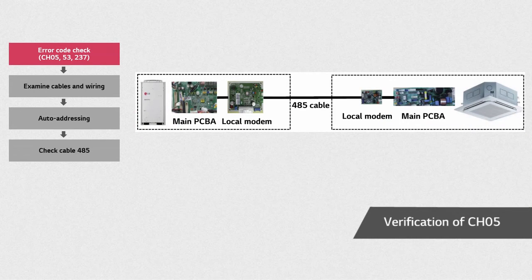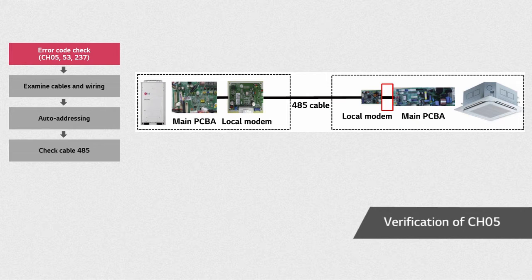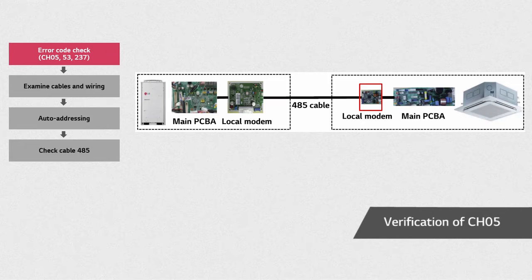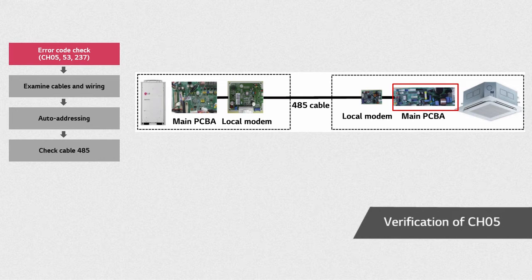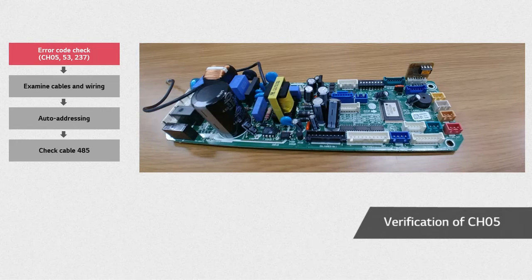When error CH05 occurs, first, check the connection between the indoor unit's local modem and the main PCB. Second, check the local modem state and replace it if any malfunction is found. Finally, check the main PCB of the indoor unit, and if any defects are found, replace it as well. When replacing the main PCB, leave the optional PCB as it is.